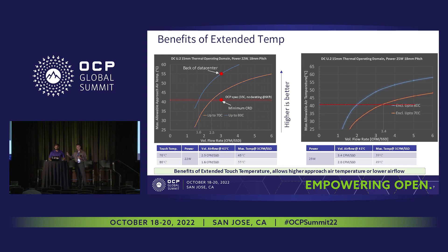If we went to a 25 watt drive, which is part of the form factor envelope, even on the 15 millimeter, we would barely not meet the 3 CFM and 35 degrees C OCP requirement with the 25 watt drive. So it is a big deal to have this feature.